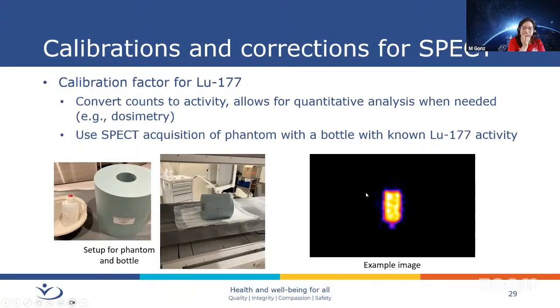So you can use that for dosimetry, to see how much activity is in that lesion, and whether it has gone down. So we needed to do this for all cameras. For all 20 cameras, again, we needed to do this. But before we could image this phantom, we had to decide what imaging parameters we were going to use clinically, because to image this calibration phantom, you have to image it the same way that you're going to image patients.